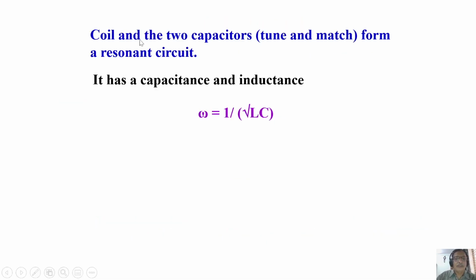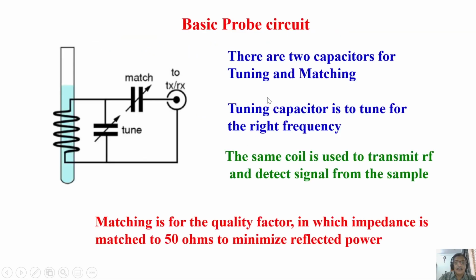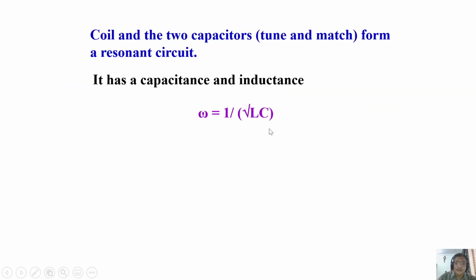Now, the coil and the two capacitors form a resonant circuit. It is like a simple LC circuit, I said. It has a capacitance and the inductance. Once you have the capacitance and inductance, you know what the frequency is. The frequency is given by 1 over root of L into C. L is inductance, C is the capacitance. If you know these two, you know the frequency for which you have tuned. That is why I said changing capacitance is there. Here, you have two tuning capacitors. When you tune the capacitors, you are varying the capacitance to match the frequency and also to match the impedance.